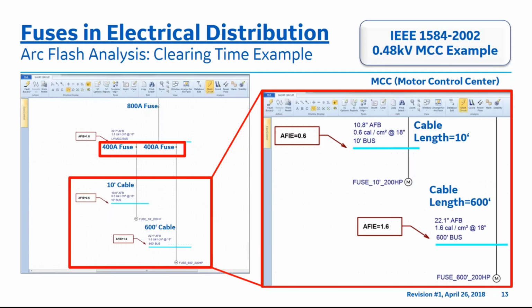The only difference is, on the left, there's a 10-foot cable with an arc flash incident energy label of 0.6 calories per centimeter squared. Now on the right, there is a 600-foot cable. Please notice the higher arc flash incident energy label on the 600-foot cable length of 1.6 calories per centimeter squared. Let's understand why there is a higher arc flash label with the 600-foot cable length on the subsequent slide by looking at the arc flash analysis report for fuses.